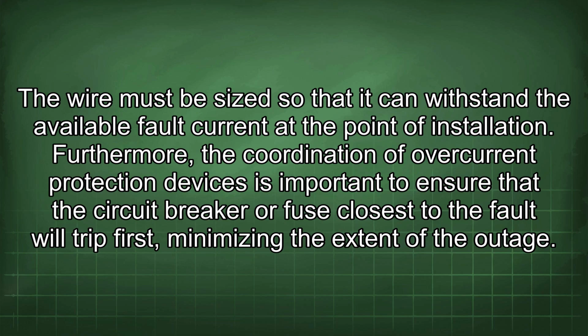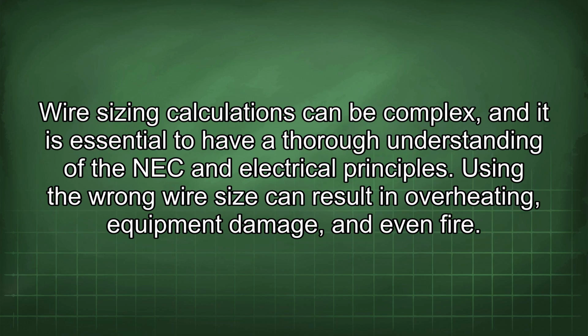Furthermore, the coordination of overcurrent protection devices is important to ensure that the circuit breaker or fuse closest to the fault will trip first, minimizing the extent of the outage. Wire sizing calculations can be complex, and it is essential to have a thorough understanding of the NEC and electrical principles. Using the wrong wire size can result in overheating, equipment damage, and even fire.